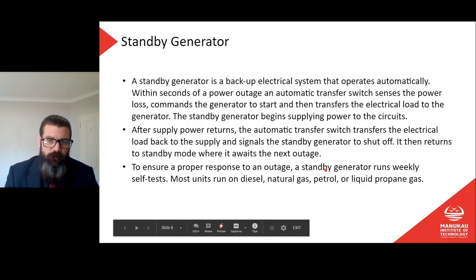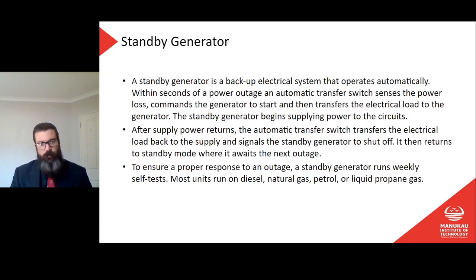Neat. That's the kind of thing I was trying to design in Timor. The automatic changeover of loads is pretty easy. Like I said, you just have two contactors, one normally closed, one normally open. The technical bit is getting the right signals to the generator to tell it to turn on, and then after it's turned on, there has to be a time delay before it switches the power outputs on, because you don't want the generator to be trying to supply power while it's starting. It needs to start up first.